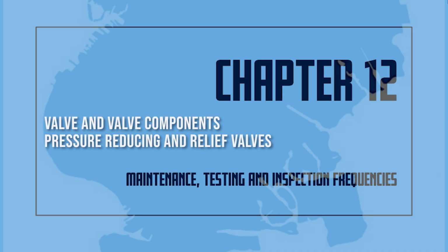All circulation relief valves shall be inspected weekly to verify that water flows through the valve when the fire pump is operating at shutoff pressure or churn to prevent the pump from overheating. Pressure relief valves shall be inspected weekly to verify that the pressure downstream of the relief valve fittings and the fire pump discharge piping does not exceed the pressure for which the system components are rated.